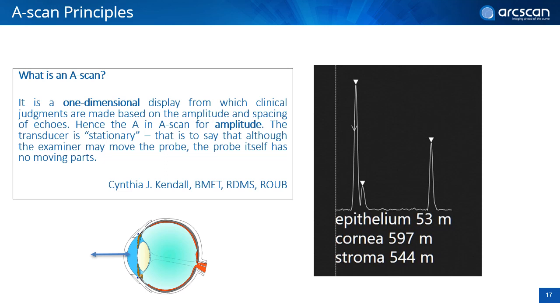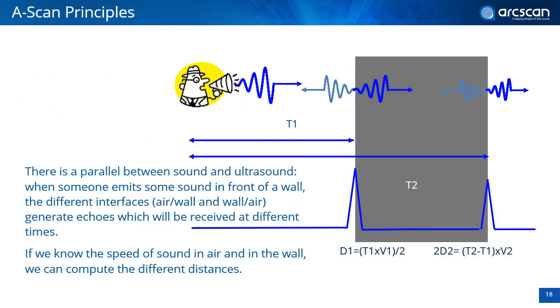Well, what is an A-scan? You're going to hear that term more as we talk about the Insight 100. It's important to understand why an A-scan is the basis for any ultrasound. The A in A-scan stands for amplitude, or the height of the peak, and it is a one-dimensional scan. Basically, one line or sound wave is projected from the front of the eye to the back of the eye. This sound wave will produce a peak or echo every time there's a change in density in its path. A sound wave is sent out, it finds a change in density and sends an echo back. The sound wave keeps traveling and encounters another change in density and sends an echo back, and so on.